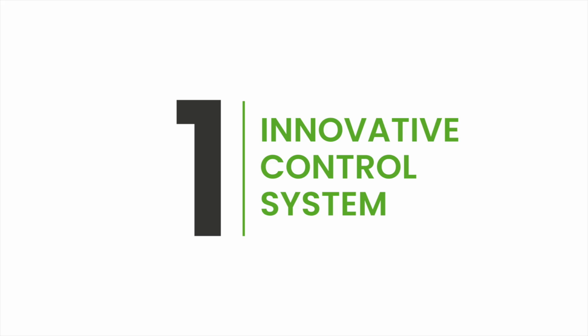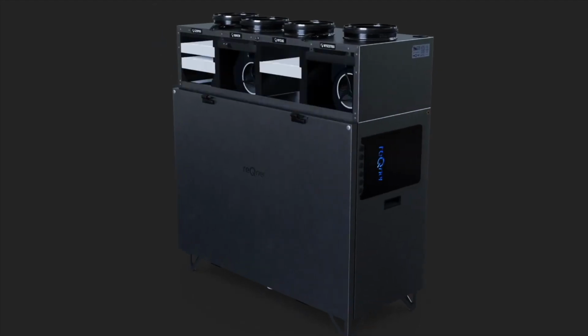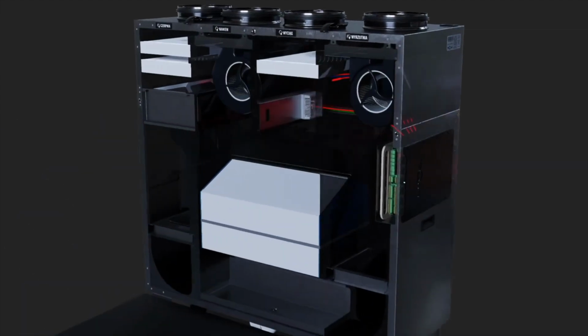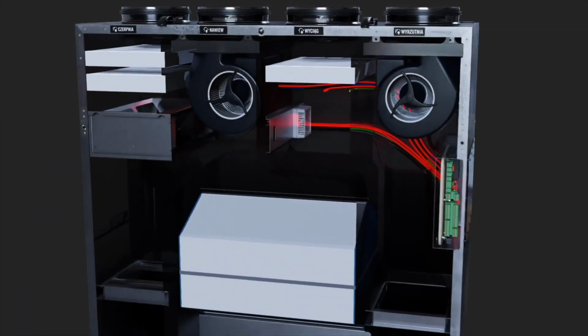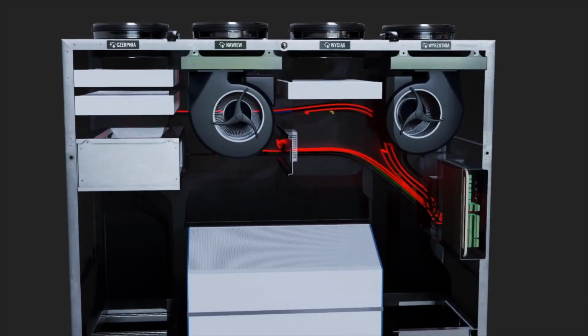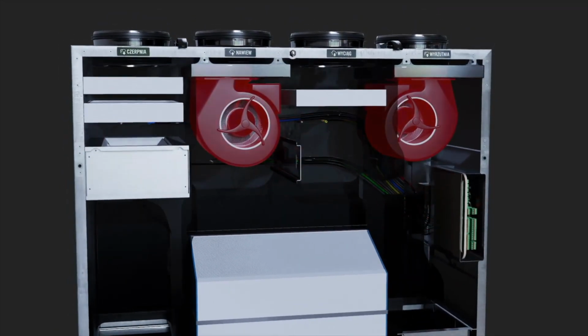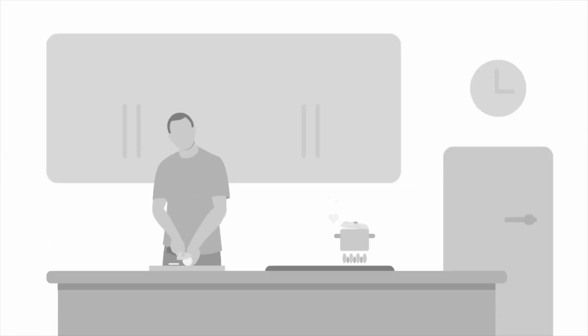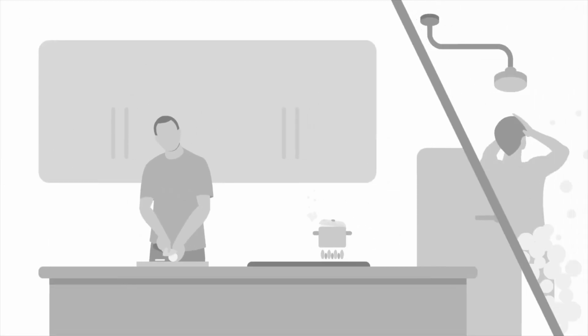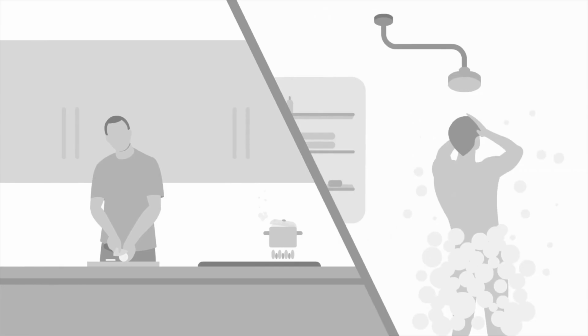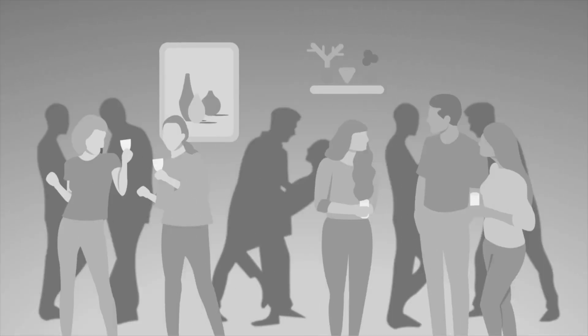Number 1. An innovative control system. The intelligent mode, in which a synergistic algorithm processes information from built-in temperature sensors, a carbon dioxide sensor, and a humidity sensor, automatically adjusting the operation of the fans to the current needs of the home. And why is that? Thanks to this, the recuperator knows by itself when and how it should operate. This ensures maximum ventilation comfort with minimal energy consumption.